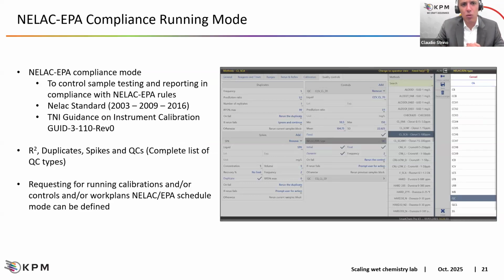Very important is that we can say that we are fully compliant with the EPA running mode, because we already saw that we can control the R square, we can define the duplicates, how to make the duplicate, and we can check the RPD percentage with corrective actions. We can automatize spike and the duplicate of the spike with corrective actions. We can define an attended number of QCs, and for each QC, as we can see from this slide, we can also, based on NELAC EPA protocol, define which kind of control we need.